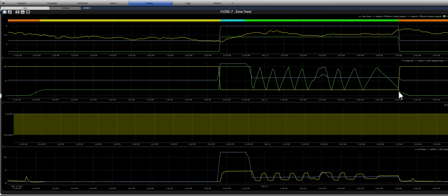And we see the box respond and basically remove all the heating. So the heating goes down to nothing here pretty quickly. And then we have the damper position opening to max, right? Here's the discharge air trend. Let's see, that's discharge air set point, and our discharge air temperature. Where is it hiding at? I missed it over here. Yes. So our discharge air temperature, boom, drops down pretty quickly to 55 or less, and matches very quickly.